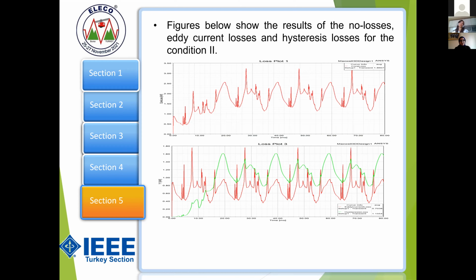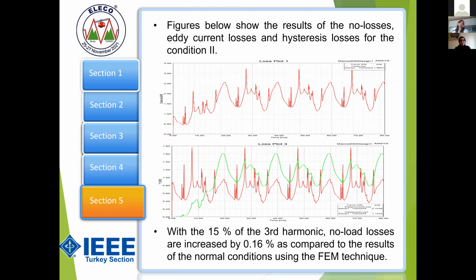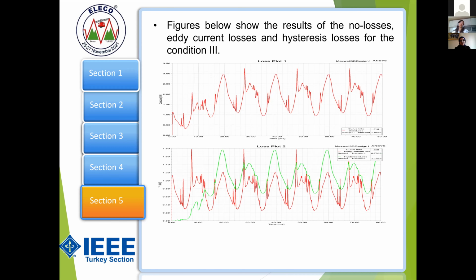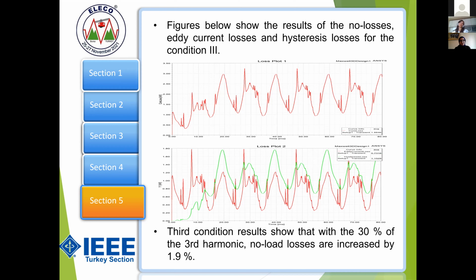These are the results. As we can see, the no-load loss during the first condition was 1.84, and in this case we increased it to 1.86. We have seen another thing: with the 15% increase of the third harmonic, the no-load losses increased by just 0.16%. But the other thing is that it is just an increase in the eddy current losses. So eddy current losses increase more with higher harmonics. In the third condition, we added 30% of the third harmonic, and the no-load losses increased by 1.9%. You can see that the hysteresis losses are almost the same, but the harmonic affects the eddy current losses more. So that means there is something in the lamination or like that.